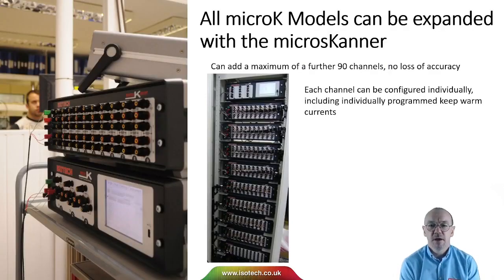All the Isotech MicroK models can be expanded with the microSKanner. You can add a maximum of a further 90 channels. We figured more than anyone would ever need, but we've got one client using 90 channels. And each of those channels can be individually programmed. You can configure an individual keep warm current, so there's always a constant current flowing through the SPRT. And you can configure the channel uniquely for the sensor type, the number of measurements per sample, units. Each channel can be individually configured.